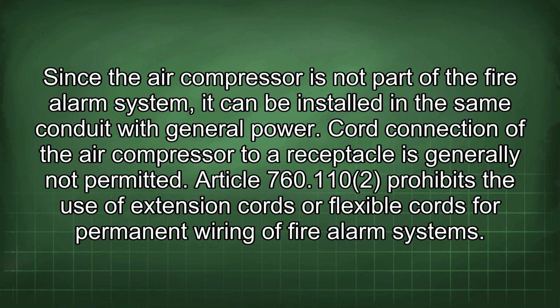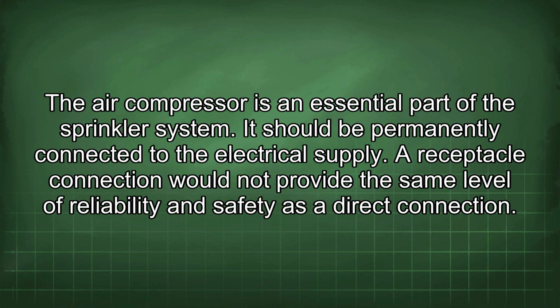Cord connection of the air compressor to a receptacle is generally not permitted. Article 760.110 prohibits the use of extension cords or flexible cords for permanent wiring of fire alarm systems. The air compressor is an essential part of the sprinkler system. It should be permanently connected to the electrical supply. A receptacle connection would not provide the same level of reliability and safety as a direct connection.